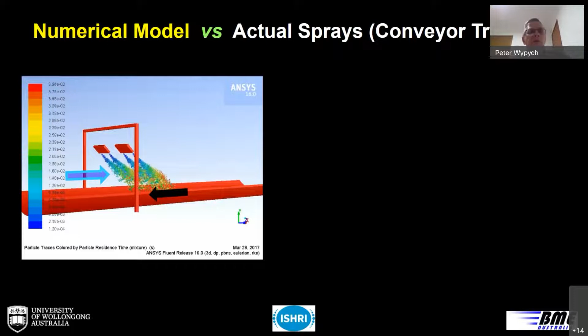This is the dynamic model we produced, showing the deflection of the mist sprays clearly, but we weren't sure how accurate it would be. Once the system was installed, as you can see here, the blue arrow indicates the direction of airflow, and you can see the deflection driving the mist into the open area of the conveyor transfer where the dust would otherwise escape—and no dust was coming out. By doing side-by-side comparisons, our predictions were spot on, and we got the mist where it needed to be, even with crosswind effects.